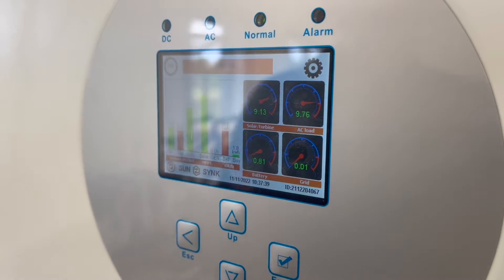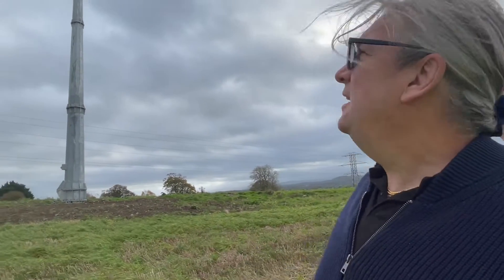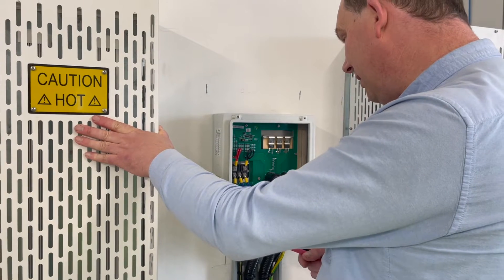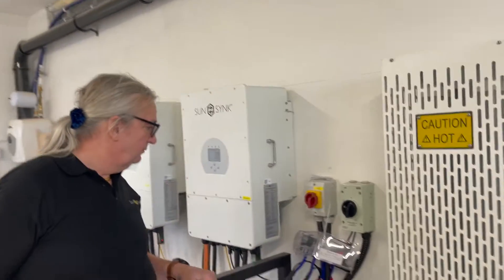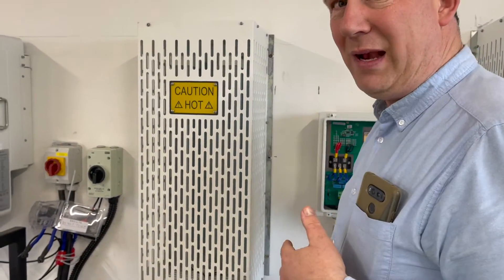So that's why it's oscillating between the two. Why is that happening — is it just a sudden rush of power taking it over its limits? So it's your unit that's detecting that. Basically when the voltage goes over about 400 volts — it may still be within parameters for the inverter, but that's actually creating the dump from that box, which is fine. You can use this to dump it if you want to. Can you adjust that? Yes, I could turn up the dump voltage higher, but I'd rather not. Because in the event of the inverter failing, we don't want the turbine going over — increasing the dump voltage effectively increases the speed of the turbine, and we really don't want that.